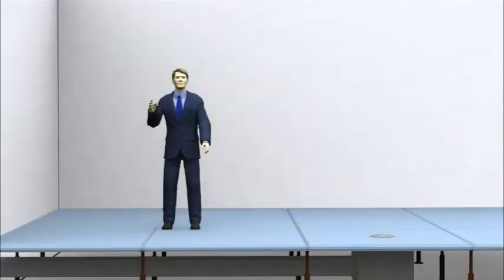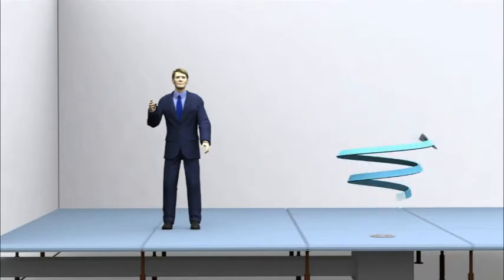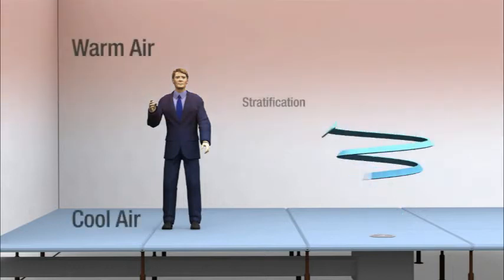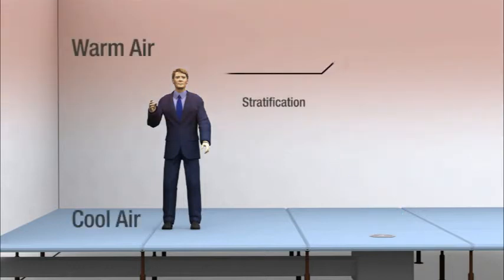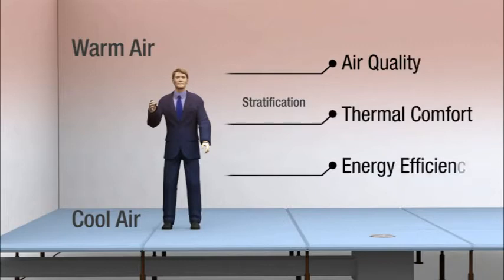The concept behind Price UFAD is simple. Air is supplied from beneath a raised floor directly into the occupied space. This causes a general upward movement of air, which, due to the buoyancy of heated air, leads to room air stratification — the key to the air quality, thermal comfort and energy efficient benefits of underfloor systems.